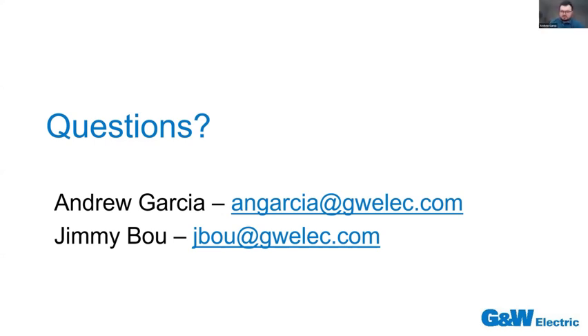Oh, that's a good question. Once again, the clip is an electronically sensed and triggered device, so it can be programmed to only trigger in response to very high levels of fault current. So you can take a look at, say, your fuses in the system, understand when those devices are expected to trigger, and make sure the clip is set to go off at a current that's higher than the fuse would respond to. And he also mentioned reactors. So Andrew gave an application for the bypass reactor. So it's a good complement to the clip, right? During normal operation, the continuous current will flow through the clip, and if there's a triggering event, then it'll transfer to your reactor, avoiding any downtime.